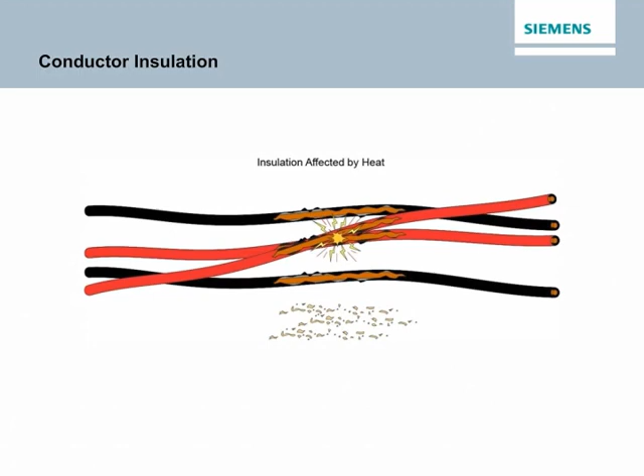Motors, of course, are not the only devices that require circuit protection for an overload condition. Every circuit requires some form of protection against overcurrent and the heat it produces. For example, high levels of heat to insulated wire can cause the insulation to break down and flake off, exposing the conductors. When exposed conductors touch, a short circuit occurs, and the circuit resistance drops to nearly zero. Because of this very low resistance, short circuit current can be thousands of times higher than normal operating current.